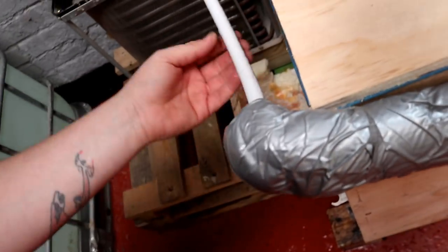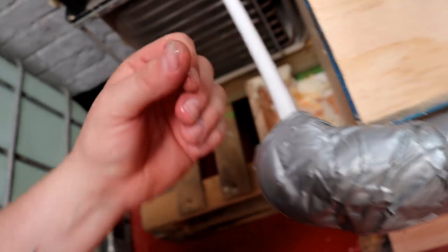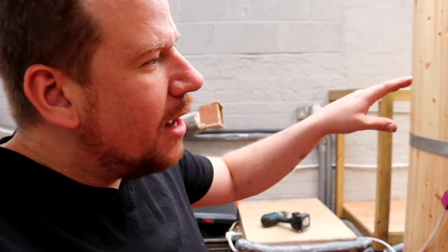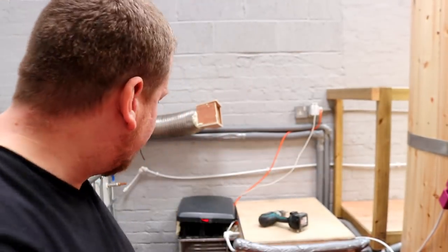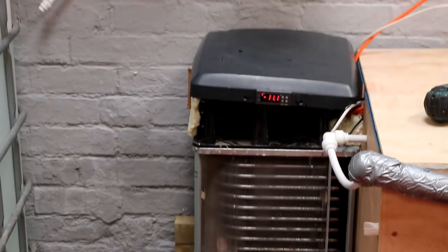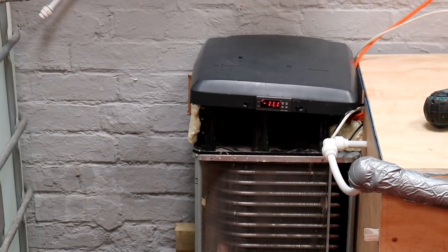we are getting ice. You see that? We're getting ice form on the pipe. So she's definitely back in business. I've also set the chiller to minus 18. We'll have a play, see if we can get her to minus 18. And then that way my thoughts are there's a bigger buffer to pull water out into the tank. We'll see, we're sitting at minus 11.1 at the minute. So hopefully we'll come back and we'll keep our eye on that for a while.